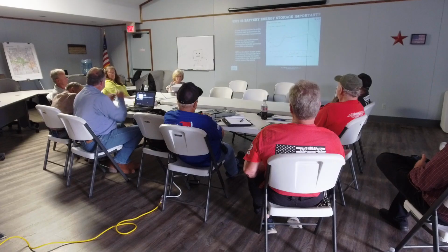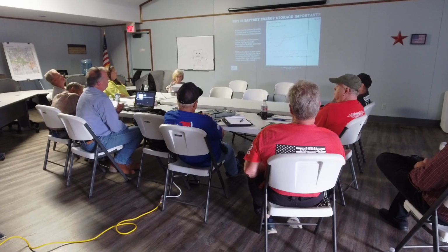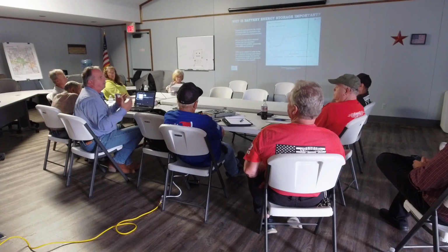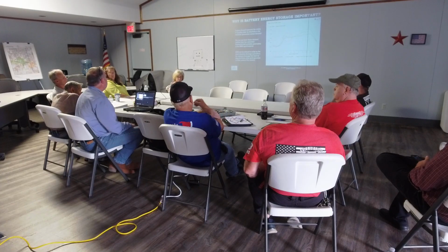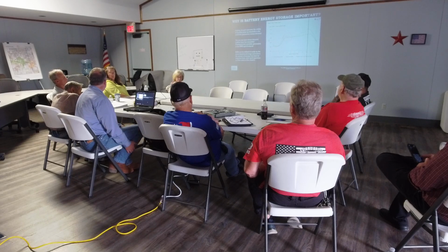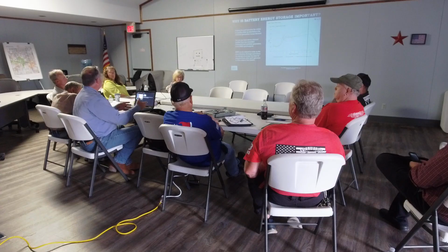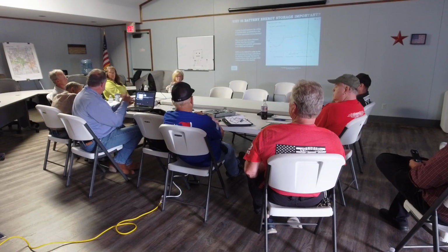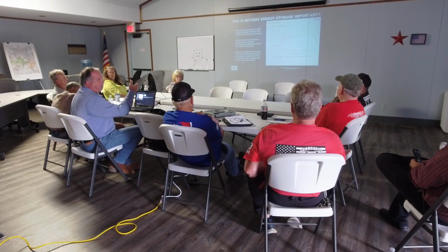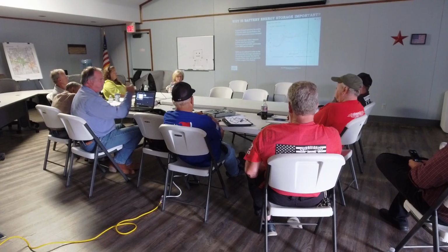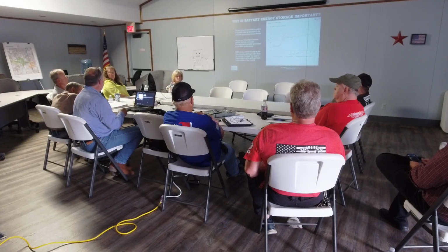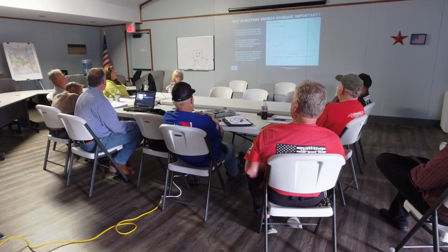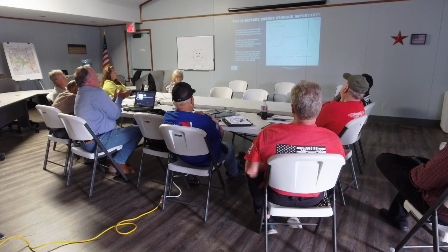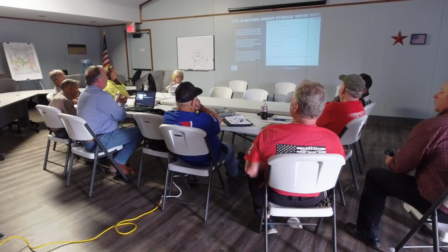Historically, we've done it with capacitor banks on poles and big capacitor banks in substations. We used to keep what we call spinning reserves, which were generators driven by either coal or natural gas. We kept them spinning all the time, burning a little bit of fuel but not actually putting out any electricity. It was then much quicker to turn them back into generation because we didn't have to bring them up from zero. But it still takes anywhere from 8 to 15 minutes on a spinning reserve to get it onto the grid. A battery can do it in 2 milliseconds. 2 milliseconds. So from a grid operator's point of view, I would much rather have battery able to be dispatched.